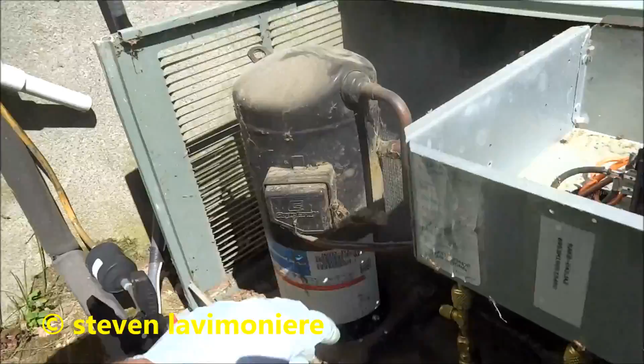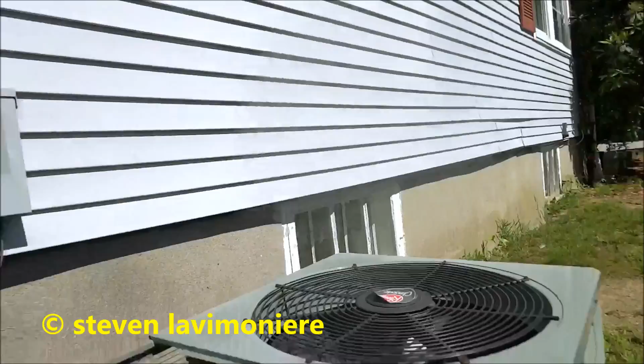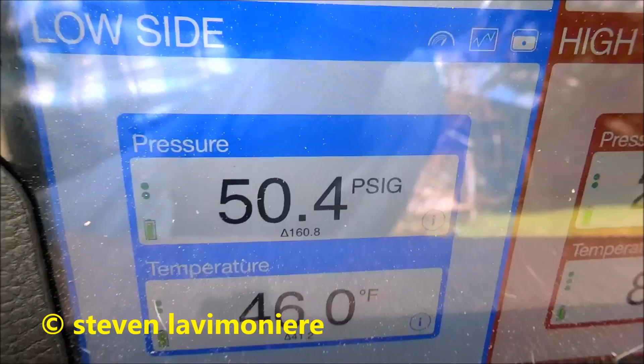Let it run for a bit, but it's probably going to be low on gas. We'll let it run for a while. So superheat, we're looking at probably about, I don't know, 50 or so. See how high it is? Just let it run for a while. It's going to be low suction pressure, I guarantee that, because of the way the airflow is. I'm not going to do too much for it because I got to give her a price on a new system anyway. I did just getting it going for now. The suction pressure is 50. She's got no airflow.